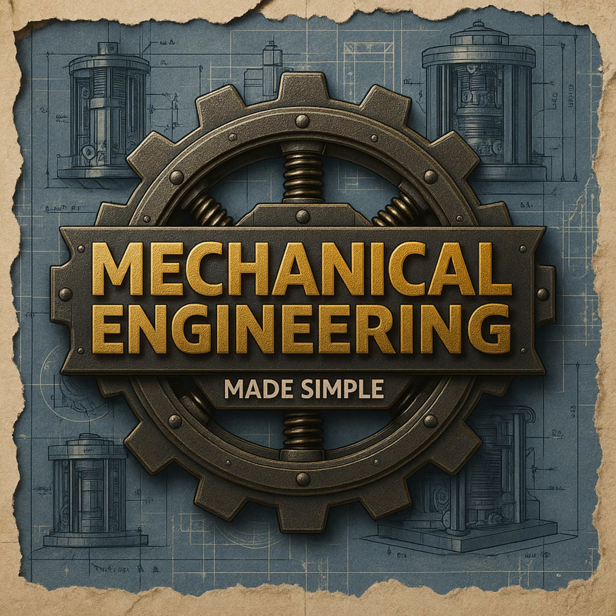Okay, but here is the brilliant part, and I guess the core engineering challenge. You now have all your liquid sitting at the cold condenser end. Right, it's stuck at the wrong end. Yeah, you need it back at the hot evaporator end to keep the cooling cycle going. But, and this is the kicker, you have no pump. Zero moving parts. So this is where that porous wick structure lining the wall becomes the engine of the entire system, right? Exactly. It's all about the wick.